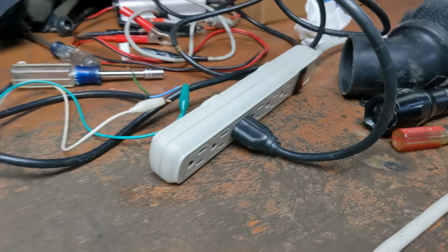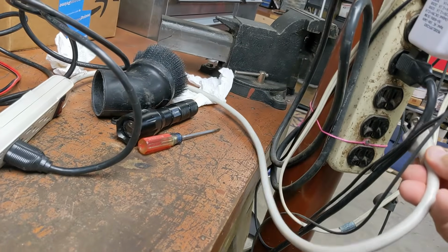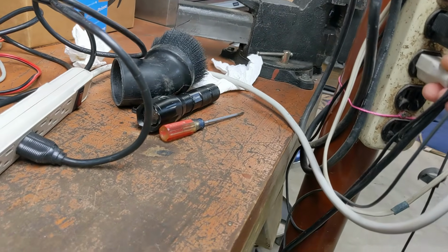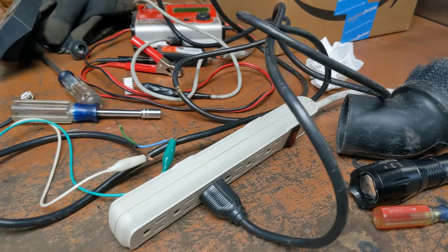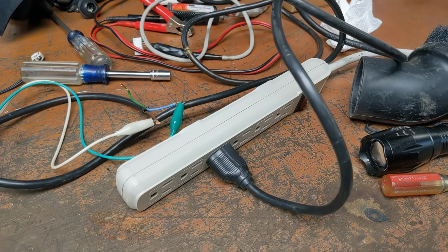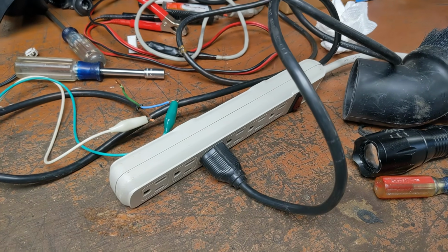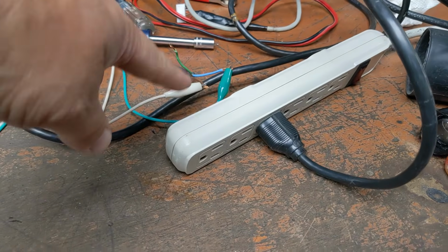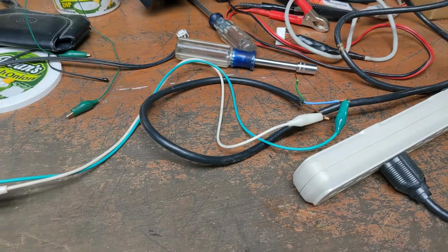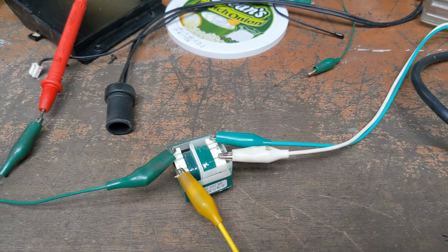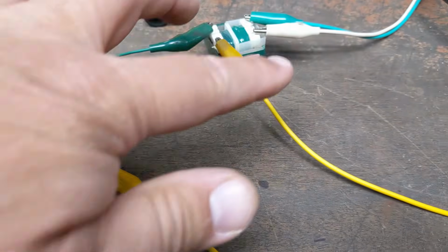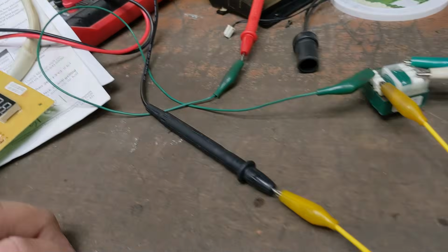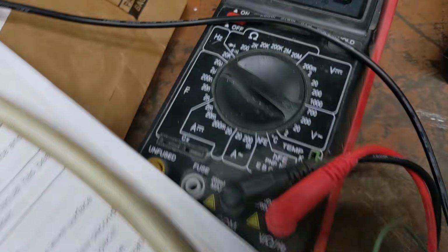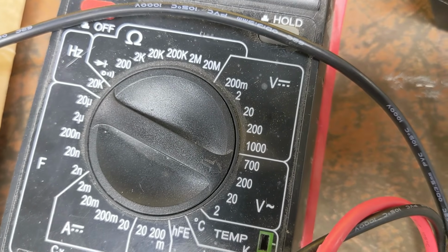That's off. Let's plug this little fella in here. Now what do we got going? 110 to the power strip, goes to this cord, goes to the alligator clips, which gives the right side 120 volts. On the other side, going over to the leads of the probe here, meter set on 200 volts AC.